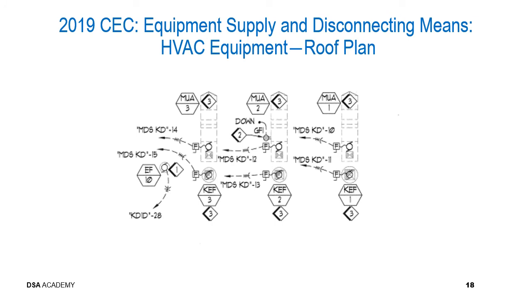What should you be thinking when looking at an excerpt from a plan view like this? That's right. Read and review every word and every symbol on every plan sheet and specification sheet for every project every time. Now, what we'd like to show is this is a rooftop view showing 3 air handler units. MUA number 1 right here, MUA number 2 right here, and MUA number 3 right here. In addition, it shows 4 exhaust fans. Exhaust fan 10, exhaust fan number 1, exhaust fan number 2, and exhaust fan number 3.